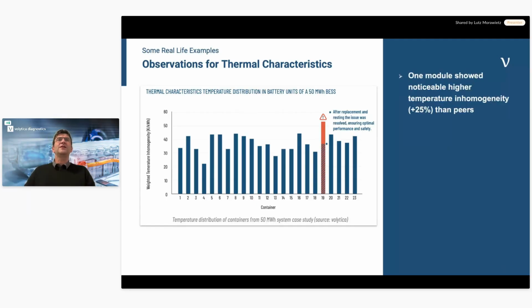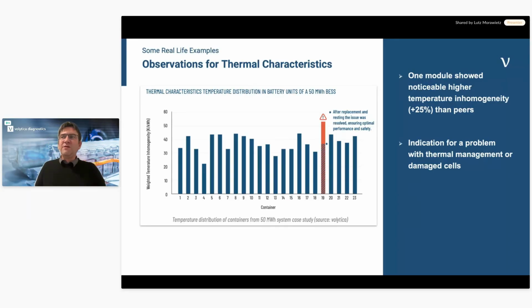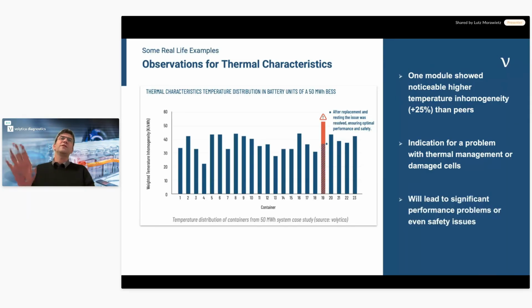We realized that one module, the orange one, showed a noticeably higher temperature inhomogeneity than its peers, more than 25% above the average. Everyone else showed normal temperature behavior. This temperature spread inside a container is an indication of a problem with the thermal management or even a damaged cell. After this check, we found this can also lead to voltage spread, which can cause significant performance problems or even a safety issue. If temperature spread is uncontrollably high, this can lead to severe problems in your system.